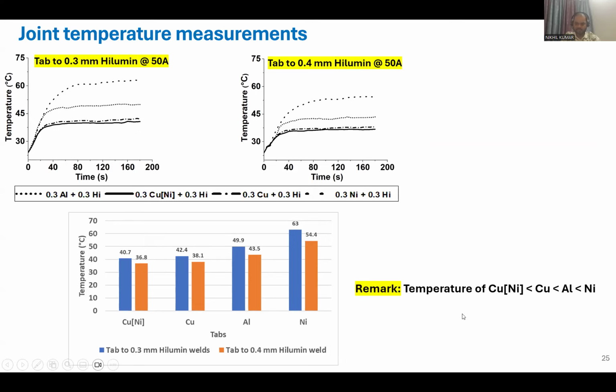A similar trend is seen here as with resistance: the lowest temperature rise is for nickel plated copper and the maximum for nickel, since temperature rise is just a reflection of resistance. The higher the resistance, the higher the temperature rise, so the same trend appears in temperature as well.